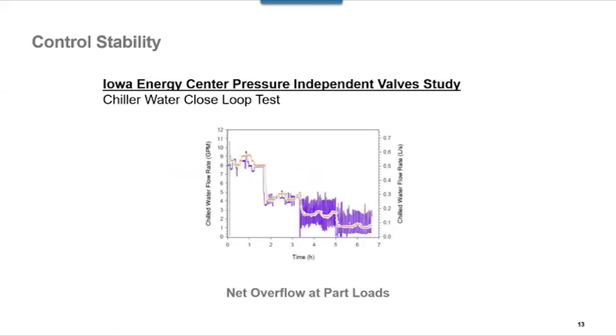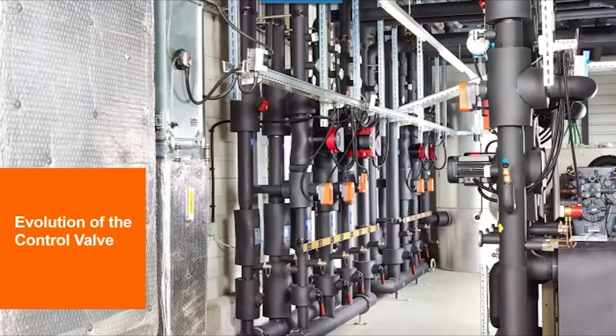Well, that hurts even more, as this graph is showing the flow going through the valves. It hurts even more when you consider your valve is going to be controlling at part load a lot more than it is at full load. That's what we're trying to accomplish with pressure independent control valves.